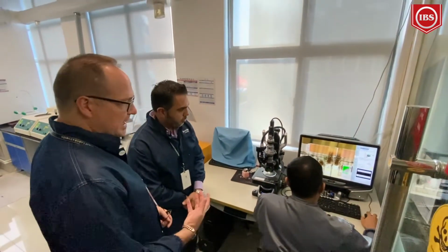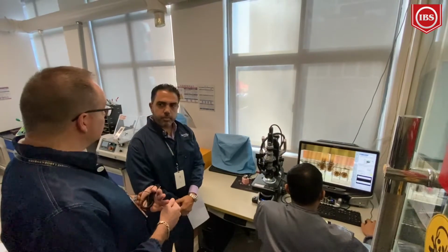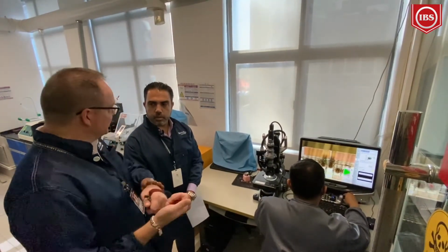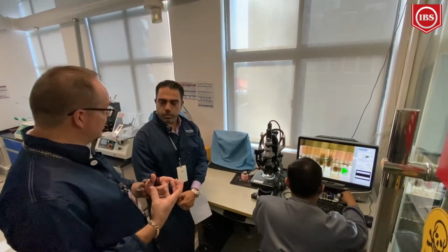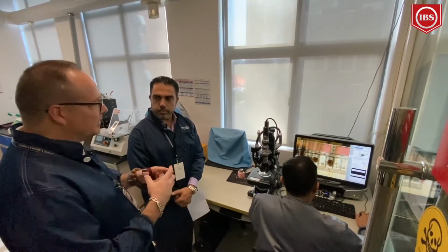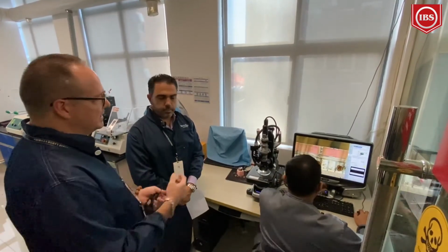But also under decapsulation, we are looking for die damage. So we can see ESD damage or electrical overstress. That part that we just saw that was shorted out, that was visible on the outside. But sometimes that damage has not materialized on the outside yet, but we can see it internally.